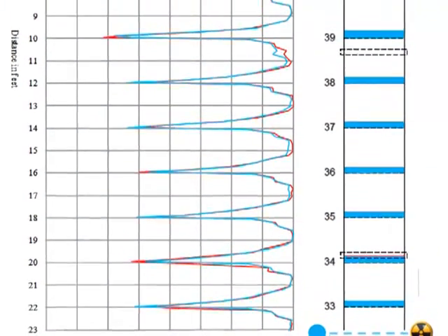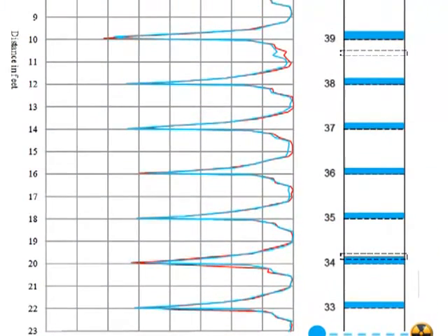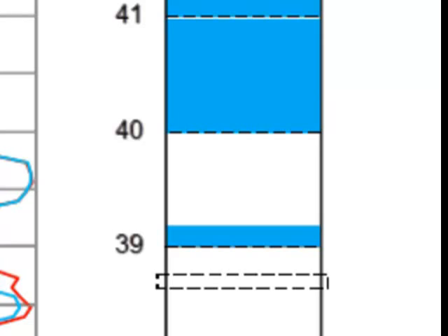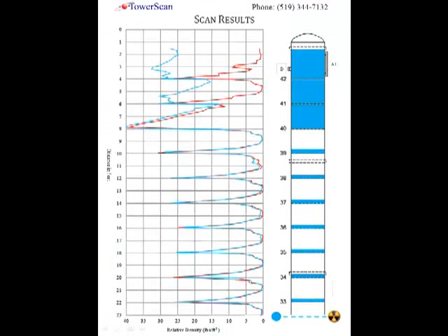Trays 39 and below showed no increase in hydraulic loadings, indicating a restriction of some sort to the liquid flow from tray 40 to tray 39, such as plugging of the downcomers, as opposed to a vapor-induced or jet flood.